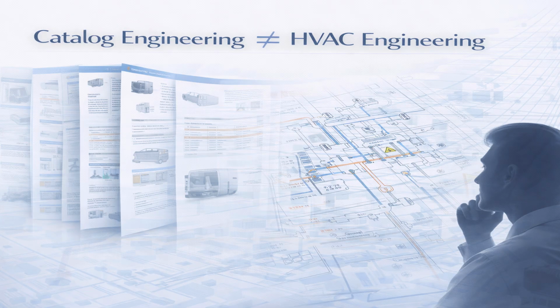Most HVAC failures are not the result of poor quality equipment. In many cases, the equipment itself is perfectly capable. The real issue usually lies in how the equipment was selected. Too often, selection becomes a catalog-driven exercise, where the focus is on matching numbers, capacities, airflows, and efficiency ratings, without fully understanding how the system will actually behave in real operating conditions. Software can calculate loads, catalogs can present a range of options, but neither can replace engineering judgment. True performance comes from understanding how loads vary, how systems operate at part loads, how components interact, and how real buildings are used over time.